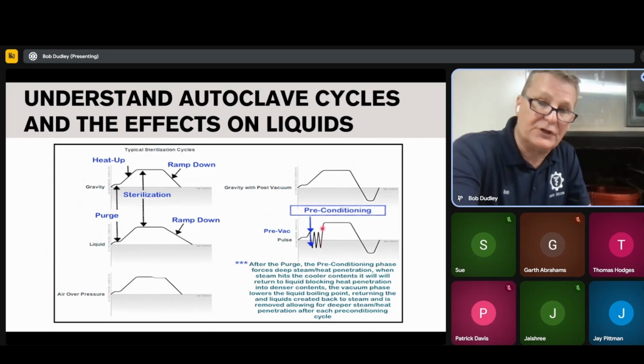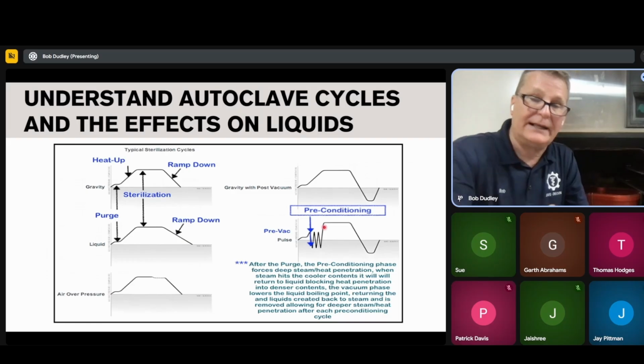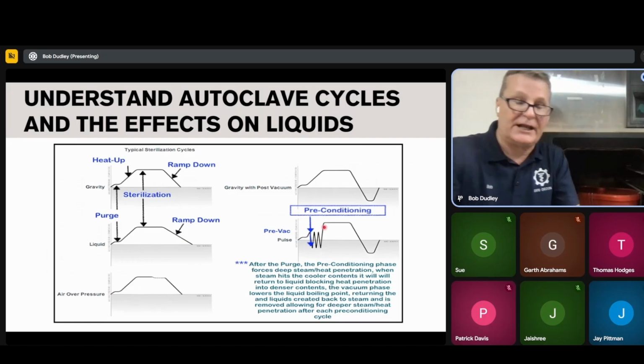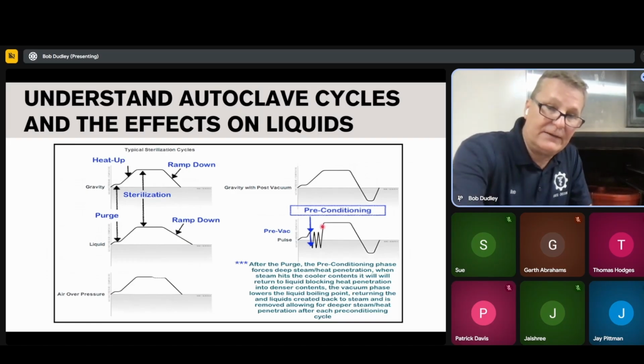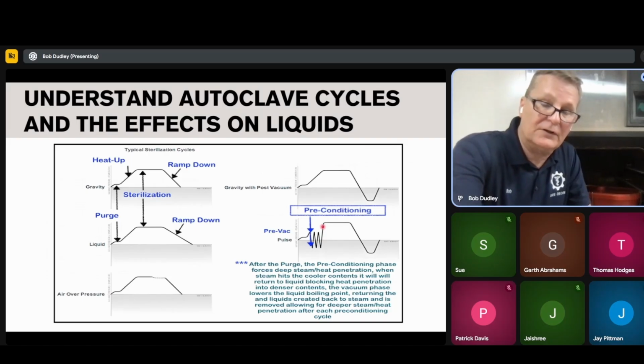So that last push comes in, and then you can see where this ramps up. This one here goes straight up, and it'll get to the same point right here. This is where it's going to do its check. And it's going to say, okay, we're at 13 PSI. We're at 118. What's our drop rate? Drop rate is good. We're going to push to sterilization. We're going to double check, go into sterilization.